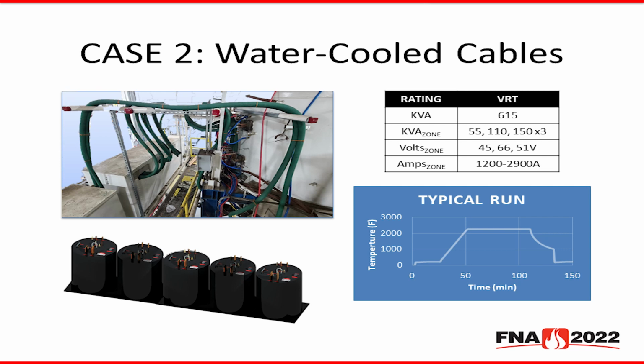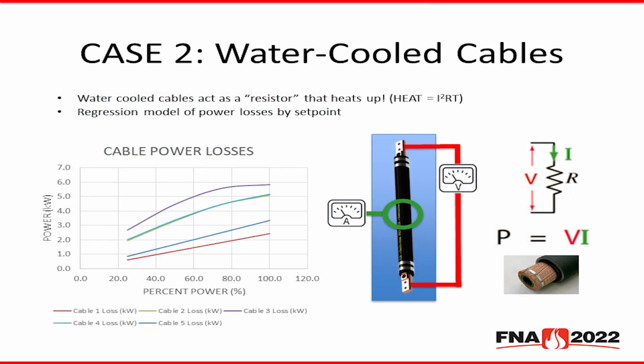The water-cooled cables in this case consisted of 4 14-foot cables, 4 18-foot cables, and 2 20-foot cables. In the picture here, you can see the water-cooled cables draped over the catwalk between the VRT power supply and the furnace chamber. So the power loss in the cables was then measured across multiple furnace set points. The power loss was calculated by measuring the amperage across the water-cooled cable as well as the voltage drop across the cable. The product of that was then used to calculate the power drop.